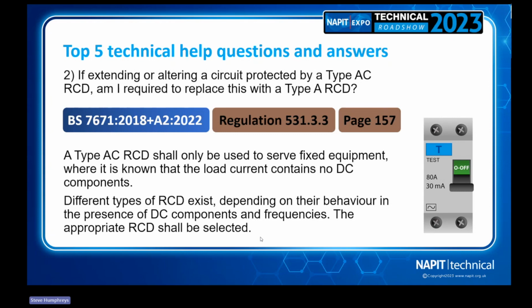It does depend on manufacturer's instructions and obviously the design of that circuit, ultimately what type of RCD you put in. For instance, a Type A will cope with DC components up to 6 milliamp. Then we've got a Type F, which will do up to 10 milliamp. And then you've got your Type B, which is your rock and roll, all singing, all dancing one that will detect smooth DC residual current and trip. So that's the answer for that one, really. It does depend on the type of circuit and the equipment that's on it.